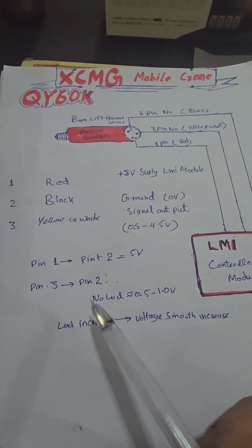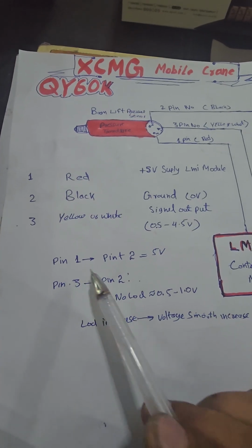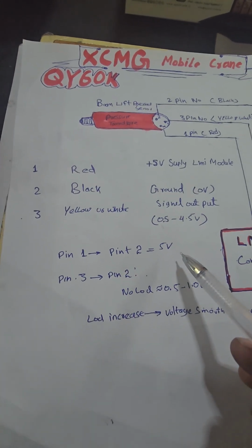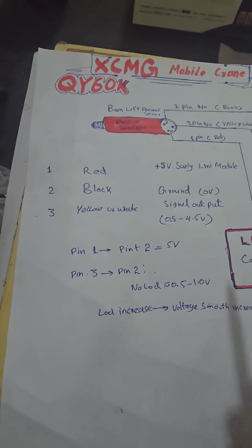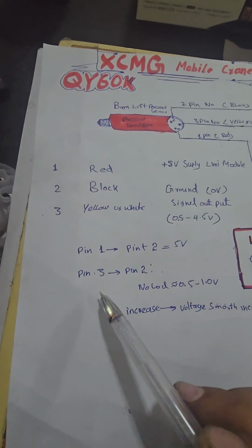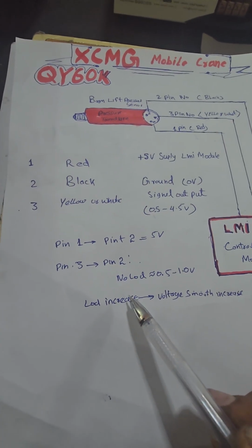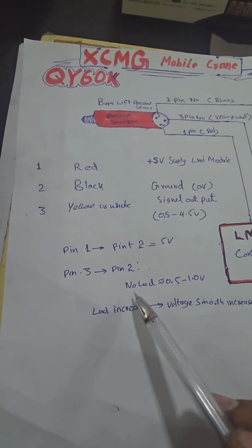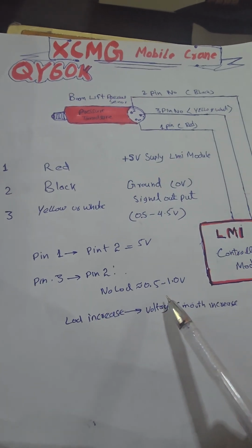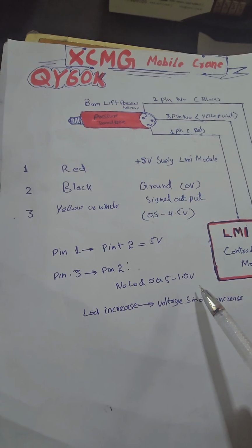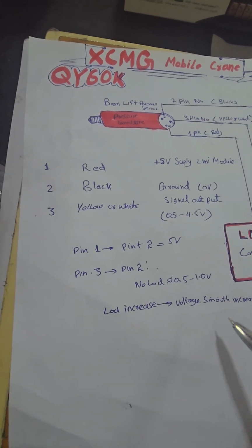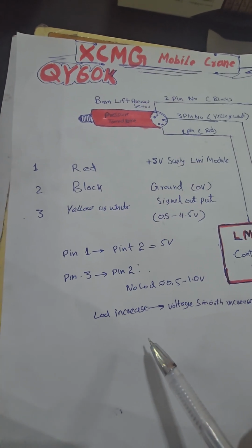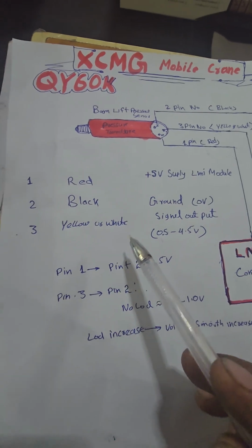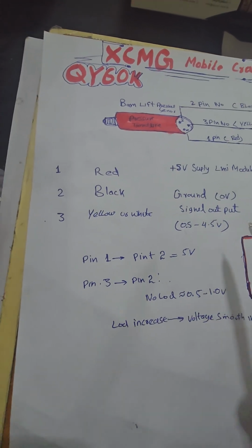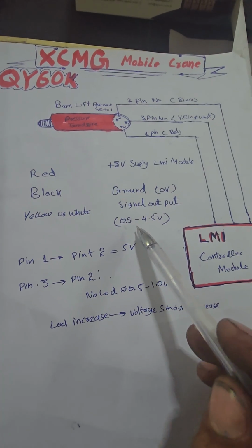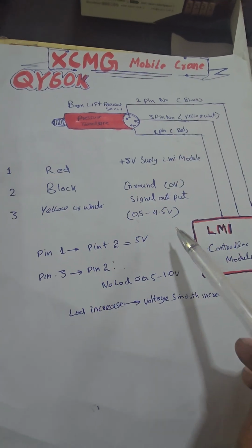When you test with a multimeter, use probe on pin number 1 and pin number 2; it must show 5V, meaning your supply is correct and good. Then check pin number 3 and pin number 2 without load; this value should show around 0.5 to 1.0 volts. When you operate the machine and the load increases, the voltage smoothly increases. When you lift the boom, if the signal properly moves from 0.5 to 4.5 volts, that means your sensor is working properly.